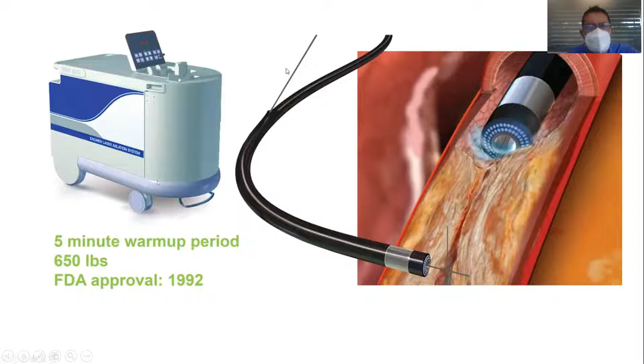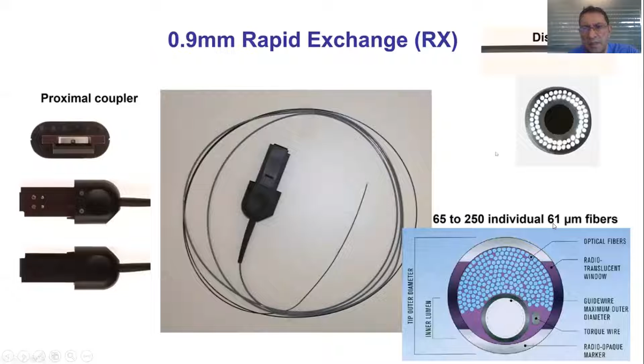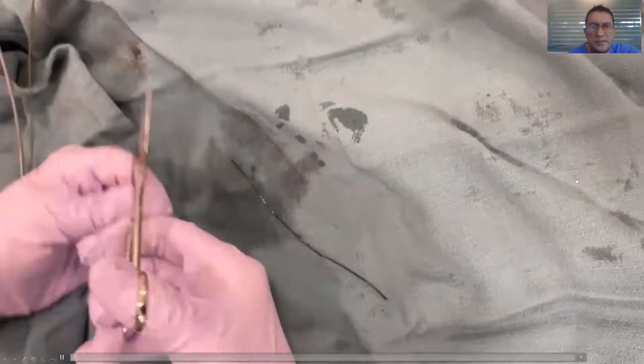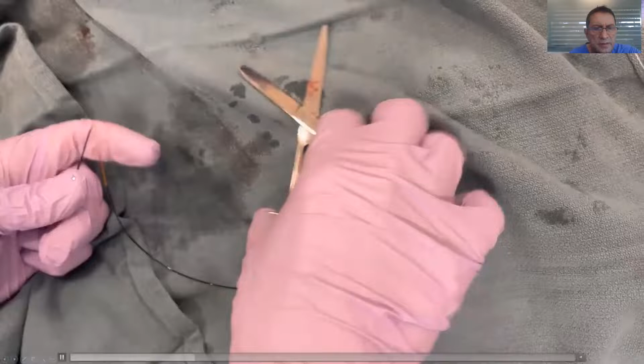And this is the catheter, the laser catheter. These are the fiber optic fibers, and this is the wire. So this is the laser catheter. This is a 0.9 mm rapid exchange catheter. This is hooked onto the laser machine, and this is the distal end of the catheter. The coronary catheter is 0.9 mm, and it has 65 fibers, and each fiber is 61 micron in thickness. So that is great engineering with this particular laser coronary catheter.